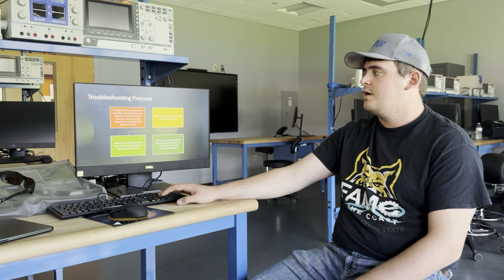Troubleshooting process. A diagnostic procedure is done to visually inspect the pump's behavior and look at the area the water is being supplied to make sure that it's getting enough. You can test the pump by manually running it or watching it automatically run, taking a flow measurement to see if equipment is getting the proper amount of water. You can use your hand to feel for pump vibration or listen for abnormal sounds.